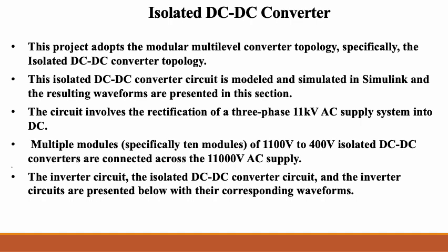The circuit involves the rectification of a 3-phase 11 kV AC supply into DC. Now, a single module may not be able to handle the 11 kV AC supply, so we built the dual active bridge and connected them together so that the input side is able to handle 11 kV, while the output was still maintained at 400 volts. So a single module was handling 1,100 volts, and the output was 400 volts.